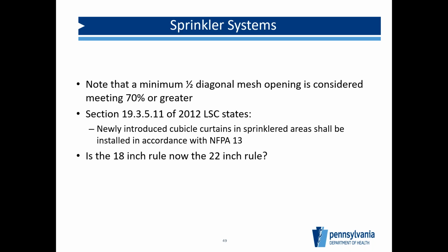And a lot of us know the 18-inch rule down from the sprinkler head to keep all our storage and everything. So is that now the 22-inch rule? And no. Everything else is 18 inches. They did not change that, but they did change the privacy curtain for new privacy curtains to 22 inches. I know a lot of folks have the red tape on the wall, or maybe the yardstick with 18 inches marked on it, so they can go around making sure that everything is down from the sprinkler head. That still stays the same. The only change was the privacy curtains.